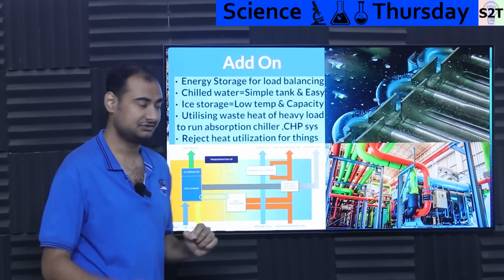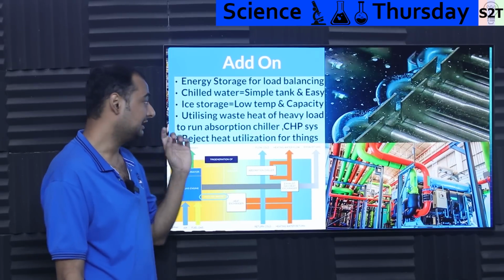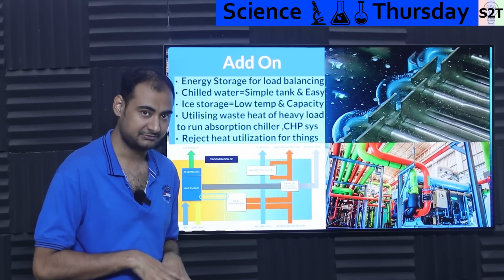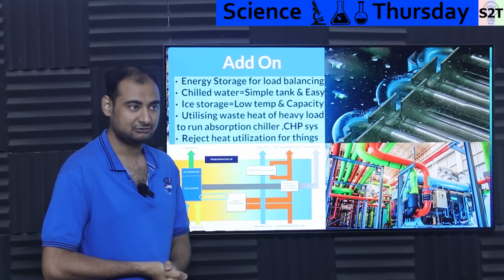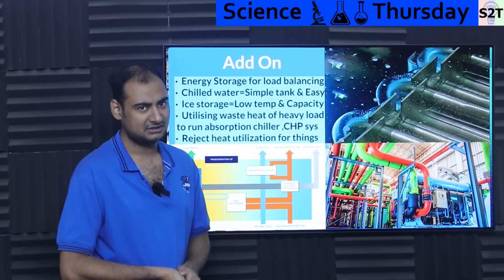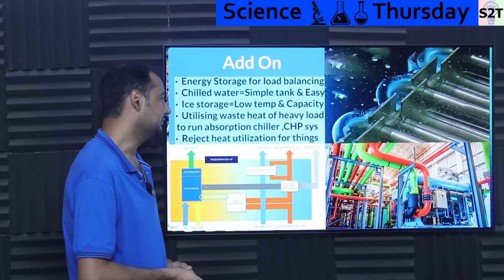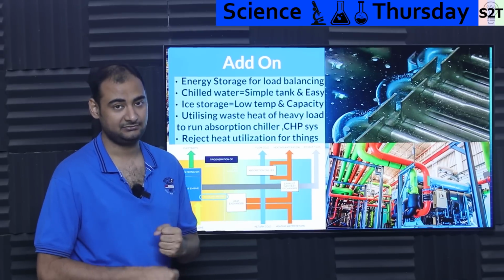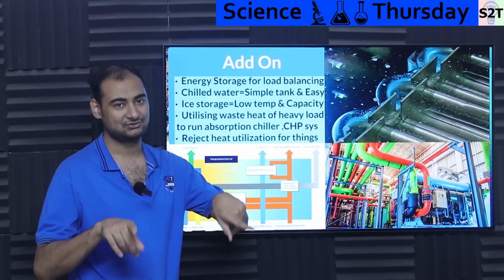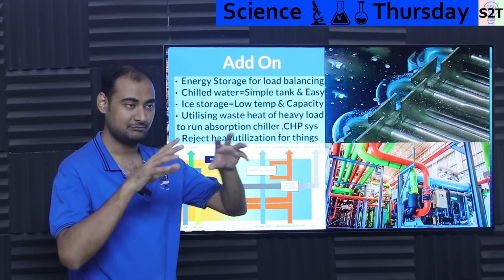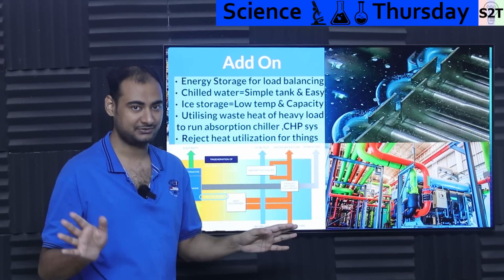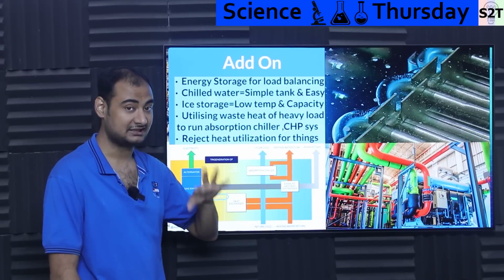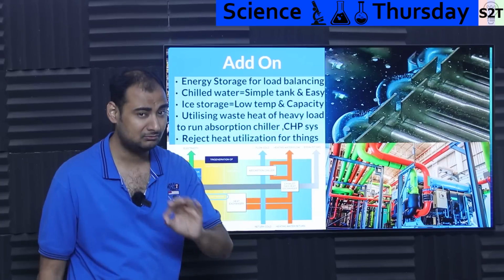Then you have its bigger brother, ice storage. Ice storage allows you to achieve even lower temperatures. If you really want to cool something intensely, you want the T delta to be low, so you're talking about 0 degrees, because water or ice melting always goes to 0 degrees Celsius. That gives you a lower temperature than 4 or 3 degrees Celsius, almost 0 degrees Celsius.